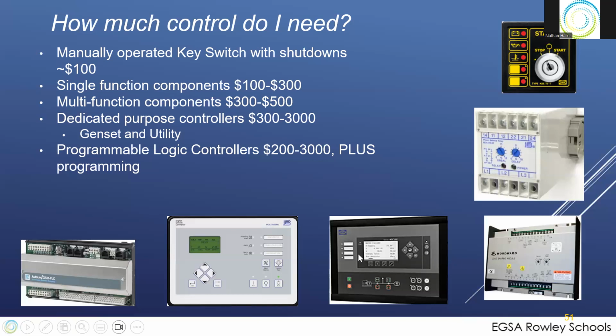Here's a DEIF controller that's a dedicated purpose controller that'll do a gen and 2 breakers. There's open and close for the gen main breaker to the load bus, and an open and close for the utility breakers if you do it all in the same controller. Here's a Basler unit. I think it's pretty much the same as this unit. I can't see, the screen is not set up the same way right now, but it's very similar functionality in the DGC 2020. And here's a PLC.